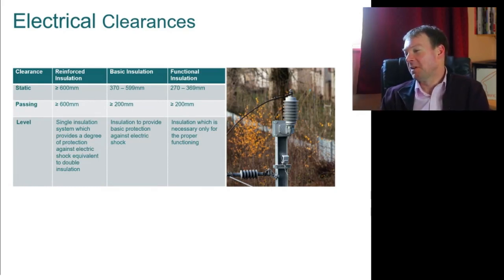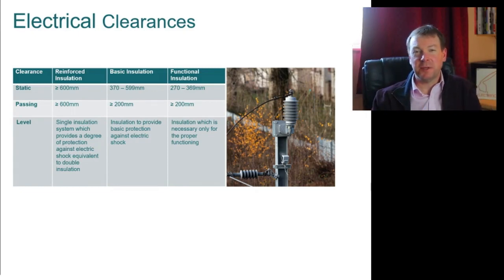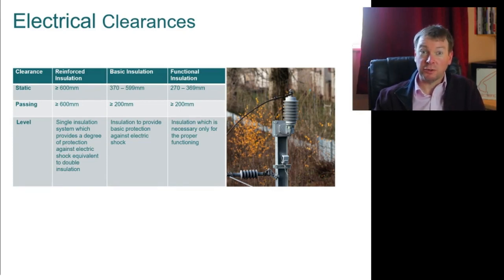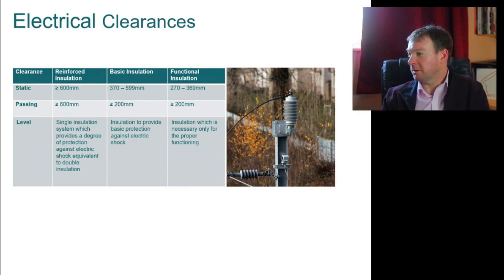I do not claim to be an LV, a low voltage bonding and integration specialist. Generally, we don't have isolating transformers - generally we can provide segregation between the electrical systems without using them. That's not to say we would never use them, but they're quite a sledgehammer to crack a walnut, really - there are other ways of achieving the segregation. We do use isolating transformers where we have AC and DC mixing, but that's a different scenario.